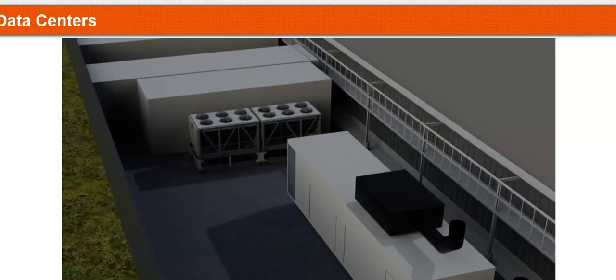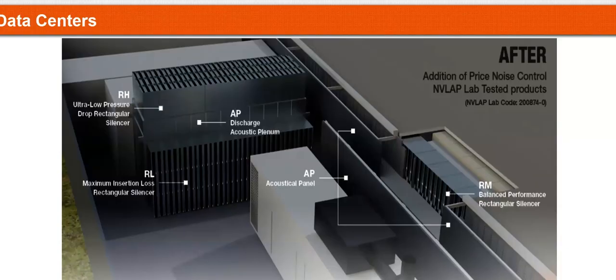So this is a quick simplified version because we cannot share any of the details of specific projects we work on with big names in the data center world. But just looking at the slide in front of you, the typical solution is what we talked about through this session: your discharge plenum with the right spacing from an air-cooled chiller to the silencer, a very specific silencer with the lowest pressure drop possible so that you don't impact the cooling performance of the chiller, and very large openings so that they can operate as well.